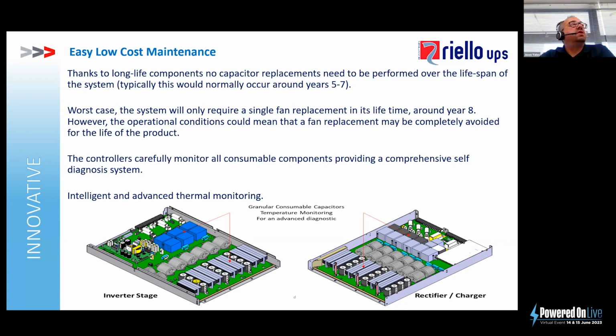Now, the benefit of this is again, it's going to reduce the maintenance. Worst case scenario, this would have to be changed halfway through the life of the product. However, depending on the operating conditions, load levels, etc., it could mean that the fan replacement can be completely avoided. So again, for the full 15 years, there's absolutely no maintenance required of the modules. Obviously, if it's a dusty environment, it would need to be cleaned. The controllers carefully monitor all consumable components, so we can provide a fully comprehensive self-diagnosing and aging system. In addition to this, there's obviously intelligent and advanced thermal monitoring.